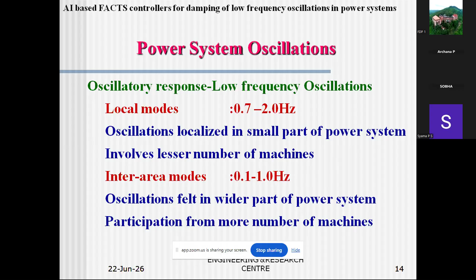Now, as I told you, this arises whenever the power system is perturbed. This is inherently happening, you cannot control that. Similarly, it is observed in all power system parameters, that is, voltage, frequency, real power, reactive power, all of which will have this low frequency range oscillation all the time. It is an inevitable characteristic of the power system. Why? Because there cannot be a situation where there is no perturbation at all in the system. This is continuously happening in the system. But you have to make sure that there is enough damping torque so that the system can sustain this. So they are acceptable as long as they decay. That means the only solution is you should have enough damping torque in the system.